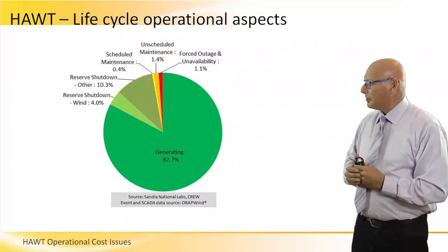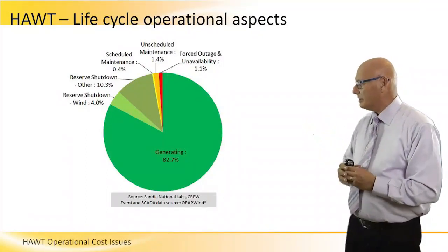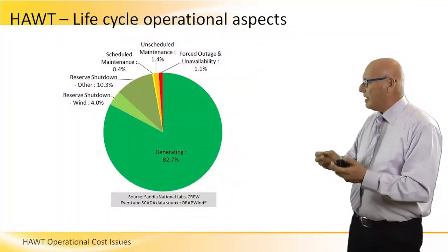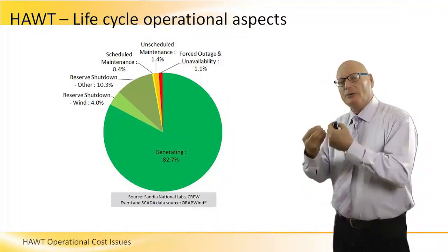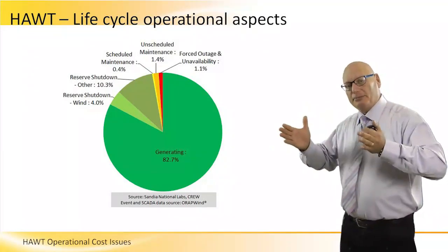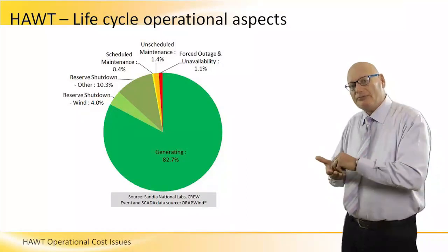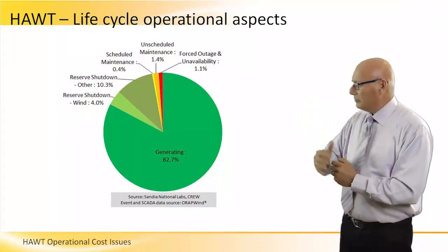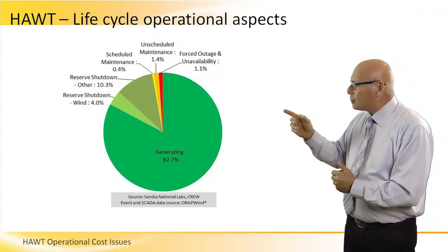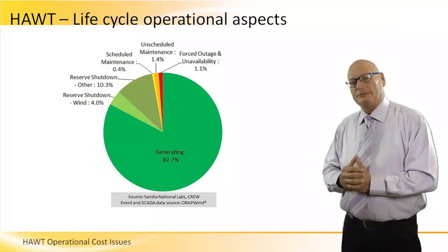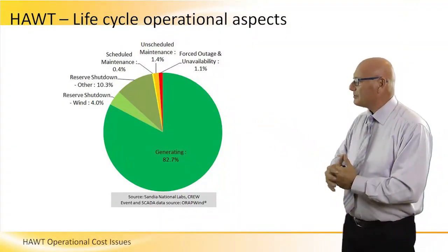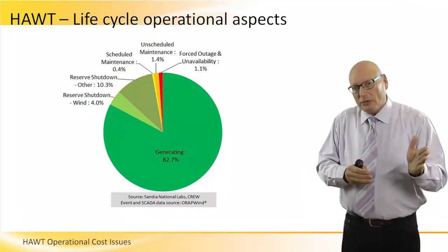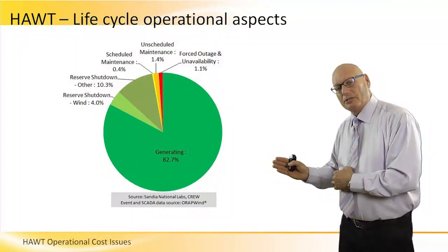This pie chart demonstrates the life cycle operational aspects of a wind turbine — this is just an example. The large green area represents 82.7% generation of electricity. So if the turbine operates 100% of the time, it will actually generate electricity 82.7% of that time. The reserve shutdown due to wind is 4% — that's the amount of time the wind is below cut-in speed or above the cutout speed.